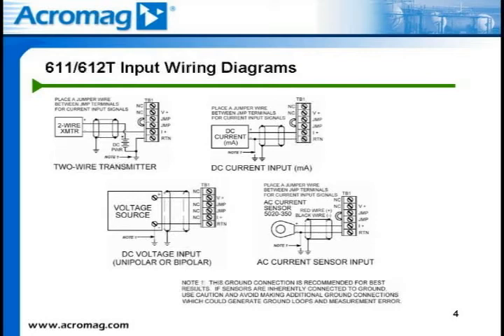The next DC current monitoring application is typical of a four-wire device, shown as a DC current input on the slide. The loop is powered from the field device and no external power supply is required in the loop. For this application, the connections are simply field device positive to the I+ terminal and field device negative to the RTN terminal. Again, a jumper is required between the JMP terminals.